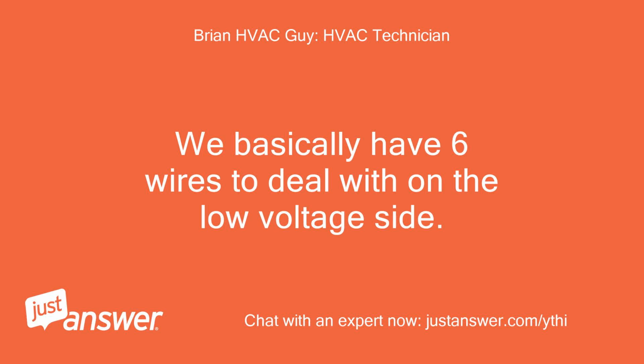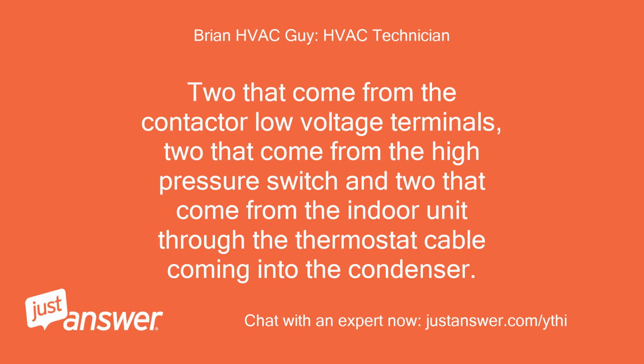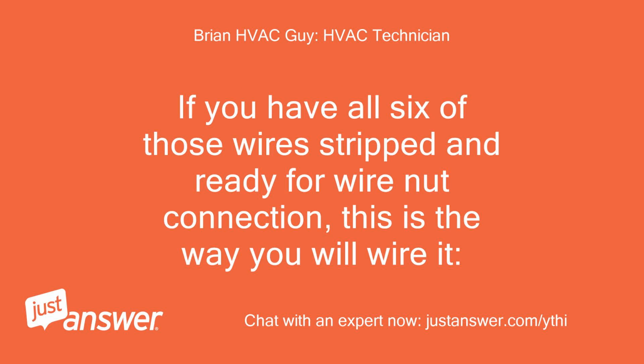Okay. We basically have 6 wires to deal with on the low voltage side: 2 that come from the contactor low voltage terminals, 2 that come from the high pressure switch, and 2 that come from the indoor unit through the thermostat cable coming into the condenser. If you have all 6 of those wires stripped and ready for wire nut connection, this is the way you will wire it.